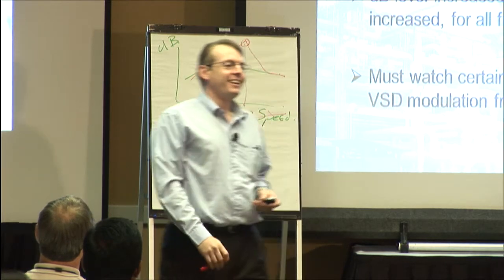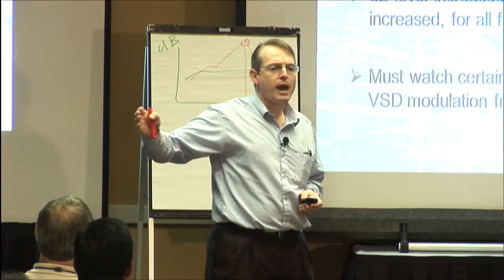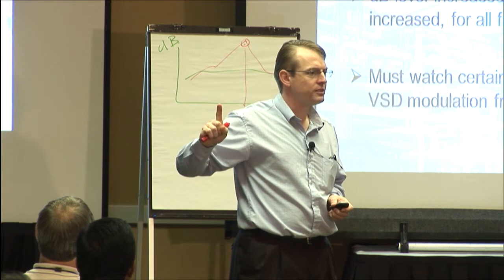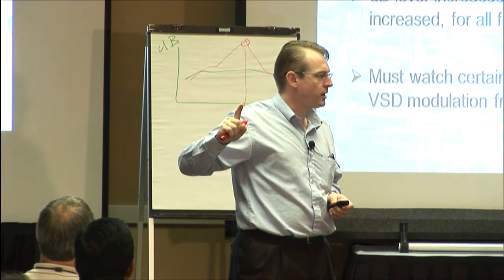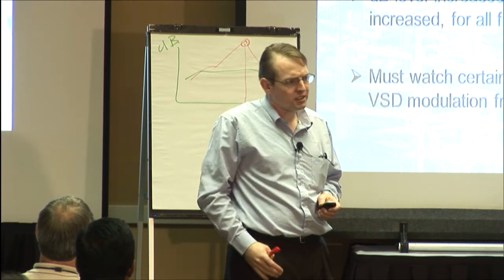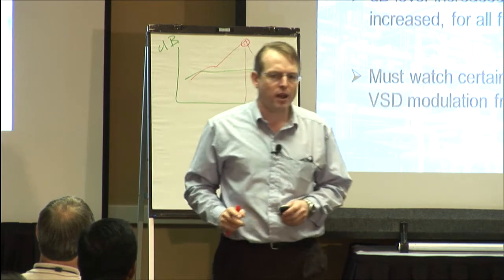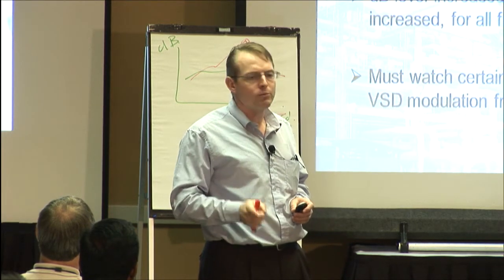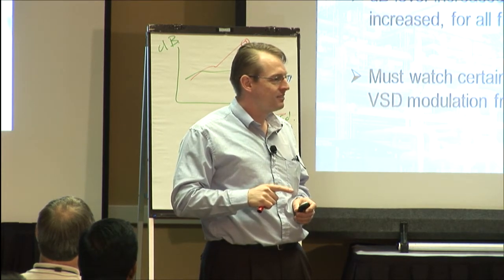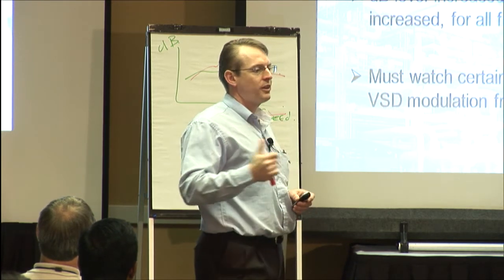That's right. Okay, no, well, 100 kilohertz, we're not going to get anything useful, right? Okay, what happens as we increase our frequency? Fundamentally, what happens? The signal attenuates more quickly, more slowly? More quickly. So you're just not going to get any useful information. So keeping that principle in mind, if we're at 30 kilohertz and we've got a problem, which way are we going to go? Up or down? Down, because we want to go lower rather than higher.